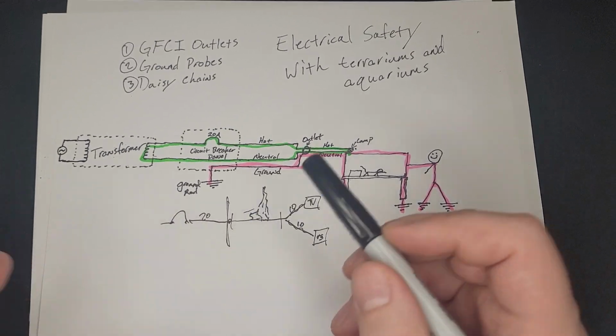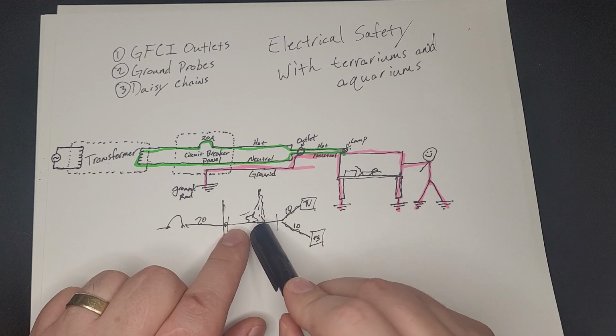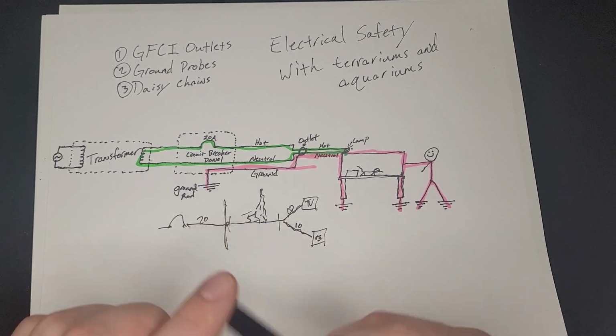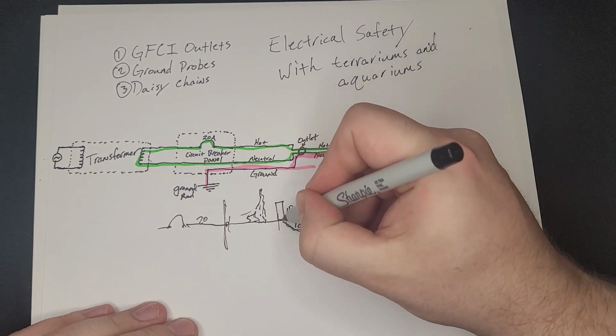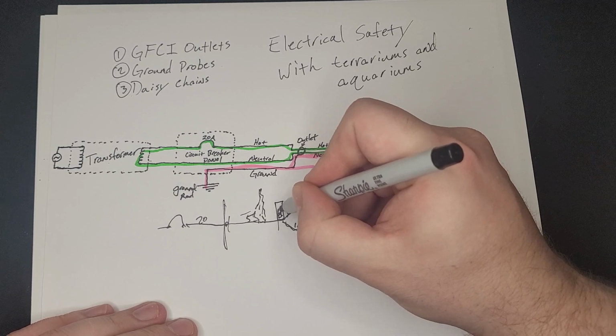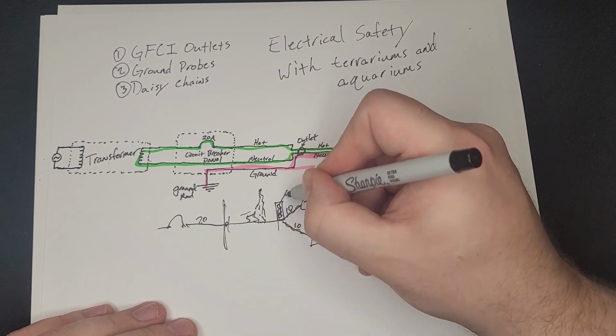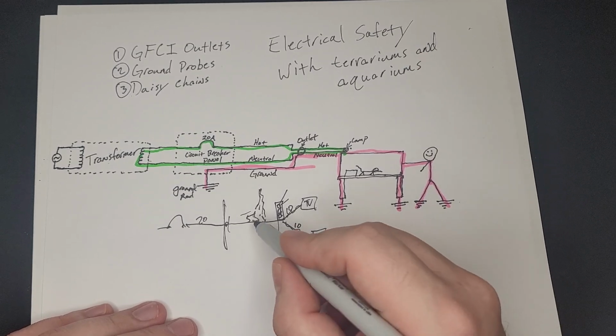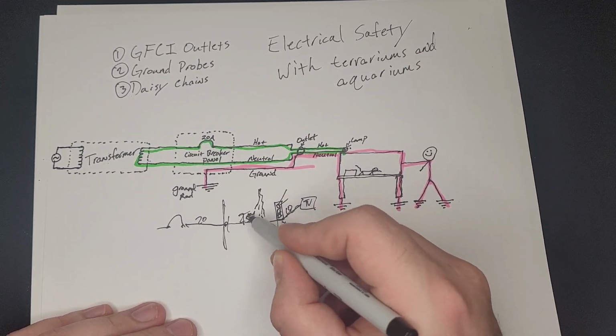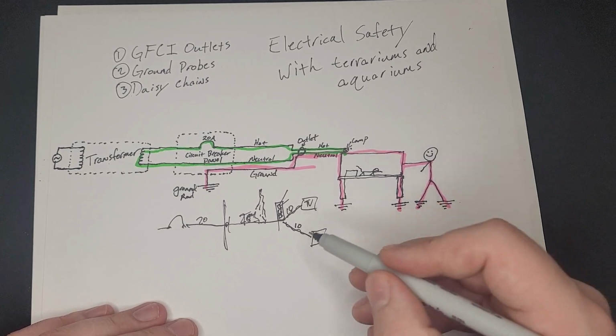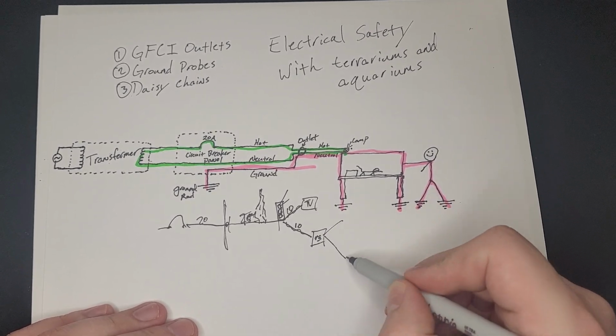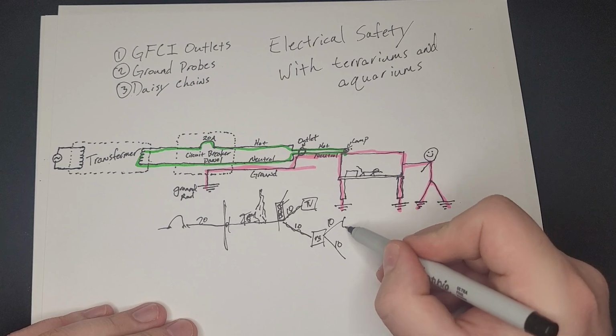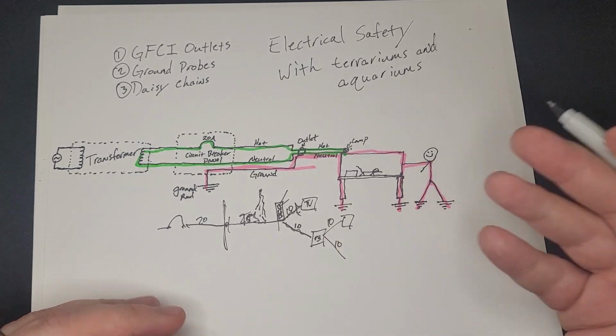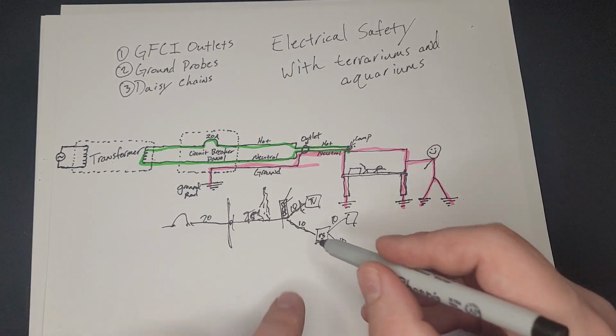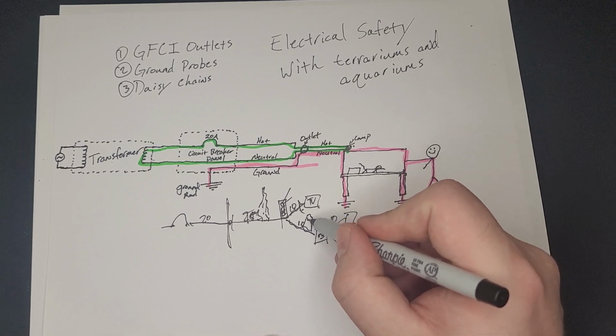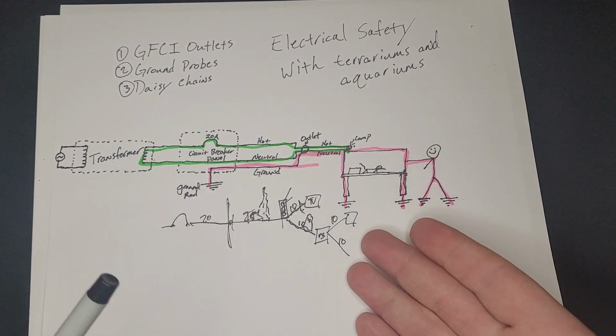You have to make sure that's true, and you also have to make sure, because these often have multiple outlets, that other people don't start plugging things in without knowing the full picture and overloading things. Even if you figure out this is rated for 20 amps and set it up properly, someone else can plug things in down the line, adding another 10 amps here, or unplug something, and create situations that can still cause a fire if other people are plugging things in. That's the real issue with daisy chaining.